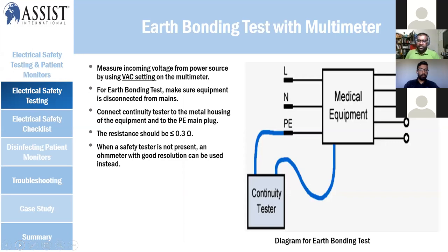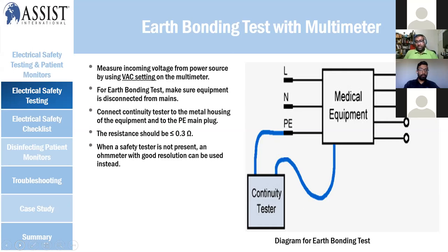The first step — earth bonding — is a very straightforward measurement. Before that, you can measure the incoming voltage from your line voltage by setting your multimeter to VAC for a direct measurement. For earth bonding, you measure from the plug point on the earth section for Class 1 devices to the equipotential point on the medical device, which is usually at the back. Using ohms resistance measurement or continuity test, the resistance should be less than 0.3 ohms.